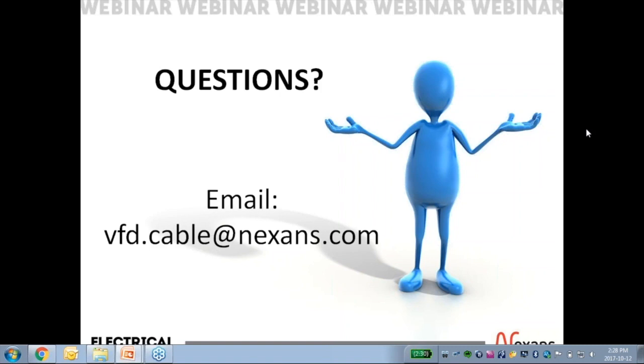There's a wealth of experience and knowledge out there, and we've talked with a few of these companies that have generated business out of troubleshooting VFD systems. In talking with them, they've stated that regardless of the drive size, fractional horsepower all the way up to tens or hundreds of horsepower, if it's a VFD, if it's a pulse width modulated waveform output, if it's not a sinusoidal output, you're going to have high frequency components. You can add filters to your heart's content. You can add shaft grounding. It'll improve it, but it won't improve it to the point of not being an issue.